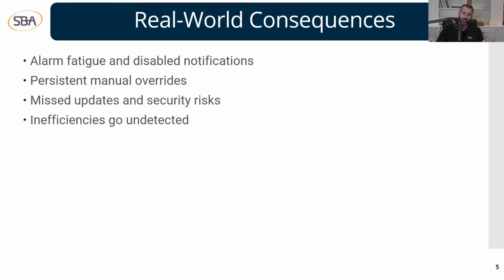During startup and checkout, you're just going around the space and nobody's complaining, so it goes unnoticed. But behind the scenes, those two coils are really going against each other, and you're running your boiler and chiller all the time. It increases the load on the system and costs you a lot of money in energy, electricity, and natural gas if you have a big gas boiler. So we need to check and make sure our sequences are functioning the way they should.